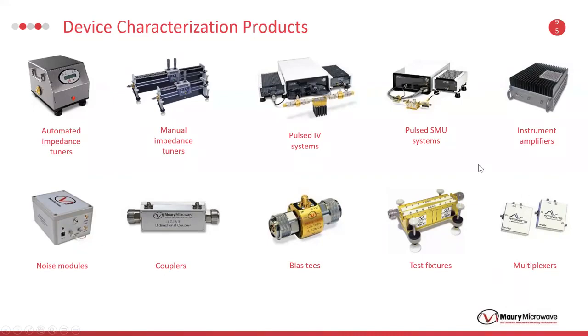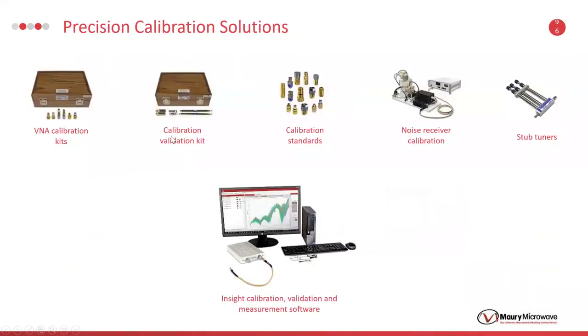This is very important: precision. Remember I was talking about the noise. Precision is very important, so use the right tools, use the right calibration kit. The VNA cal kit is very important. Take care of your calibration kit. Clean them very, very often. Clean them every time you want to use them. It's very important, especially the mechanical ones.